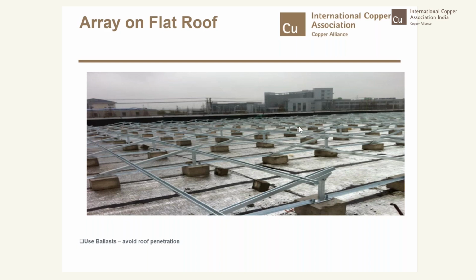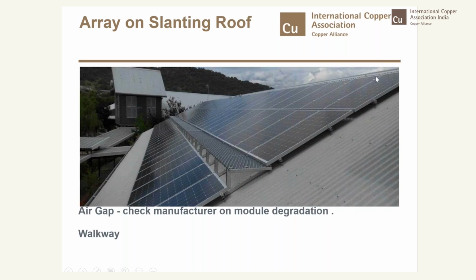And the second type of array, next slide you can see, which is commonly used, is on the slant roof. Here you will see the slant roof where the orientation of the module is along the roof slant. Here in this picture, I would like to point out a couple of errors also. One is the tilt angle which the module is expected to have in that region. It may not be correct, because you are installing it along with the truss, and this truss in the picture looks like 45 degrees. In India, you may have to install it at a different tilt angle, depending upon the latitude where you are installing it.